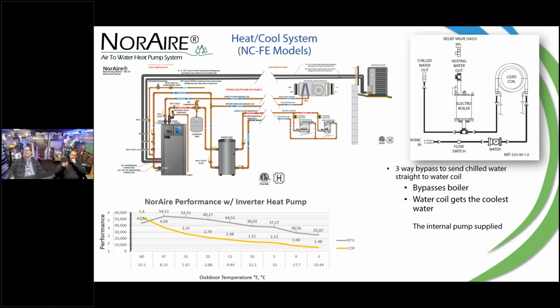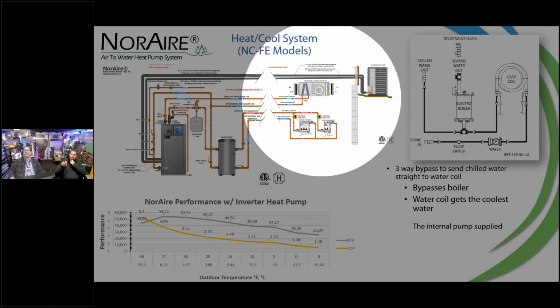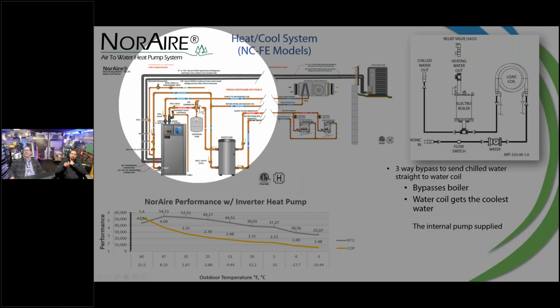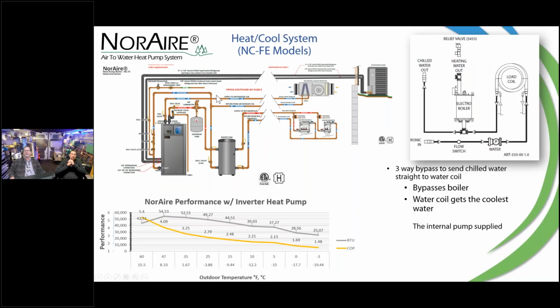I thought the diagram was pretty cool. You see a low temp air handler here, and they're taking that off the top of the unit before it gets to the buffer tank. So that's giving you an opportunity to take the hottest temperatures right out of the machine itself, not from the thermal storage, and throw it out into the space.